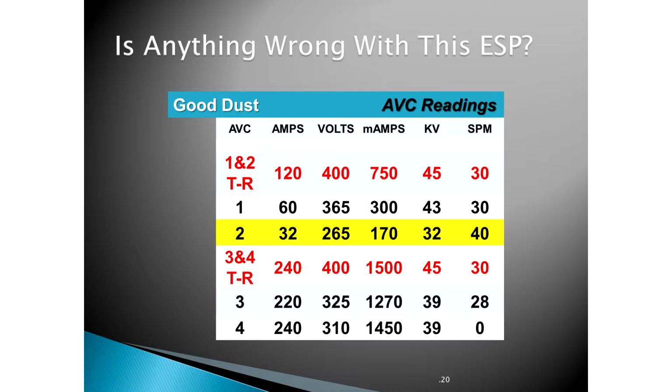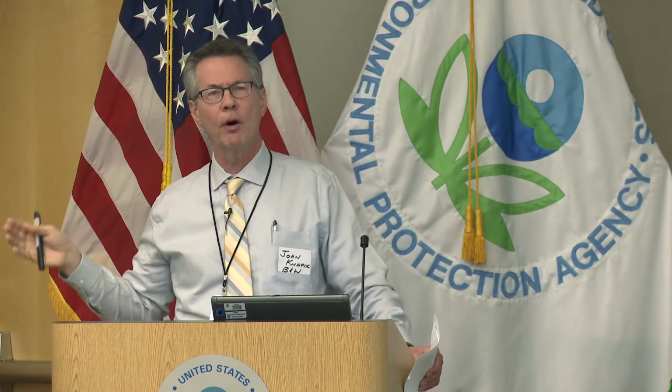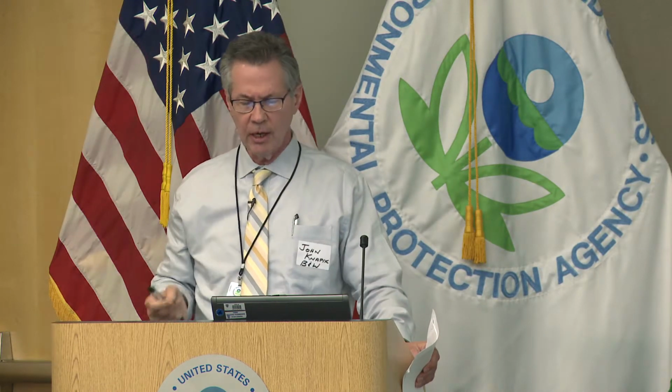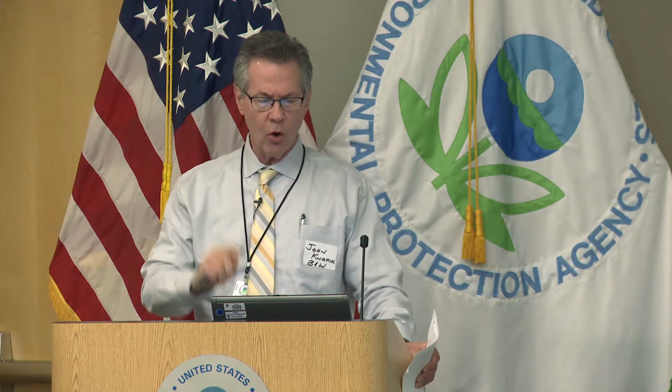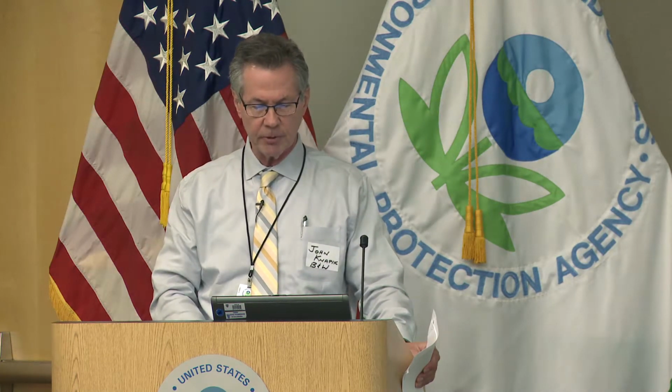And the problem here for you people to recognize is that this is with the precipitator, it's not with the process. What do I mean by process? Well, if you change coal, that might have an impact on the performance of the precipitator. Going to a low sulfur coal, a higher resistive ash, affects the whole precipitator. Process affects the whole precipitator. This is an example of just one field. It could be the rappers, which are cleaning devices on that field, are out. Could be the hoppers are overfilled in that field, but it's a single field of the precipitator.